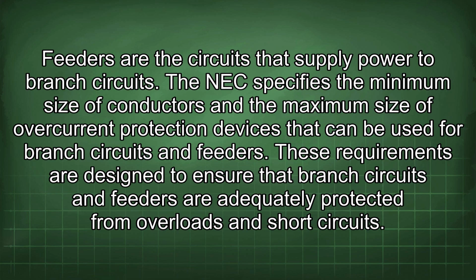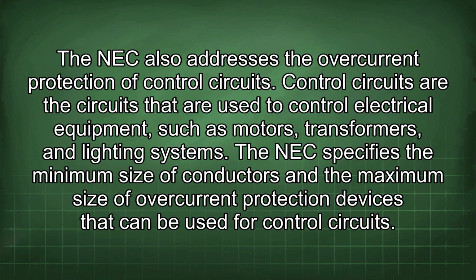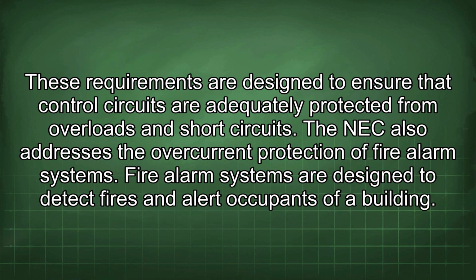The NEC specifies the minimum size of conductors and the maximum size of overcurrent protection devices that can be used for branch circuits and feeders. These requirements are designed to ensure that branch circuits and feeders are adequately protected from overloads and short circuits. The NEC also addresses the overcurrent protection of control circuits. Control circuits are the circuits that are used to control electrical equipment, such as motors, transformers, and lighting systems. The NEC specifies the minimum size of conductors and the maximum size of overcurrent protection devices that can be used for control circuits. These requirements are designed to ensure that control circuits are adequately protected from overloads and short circuits.